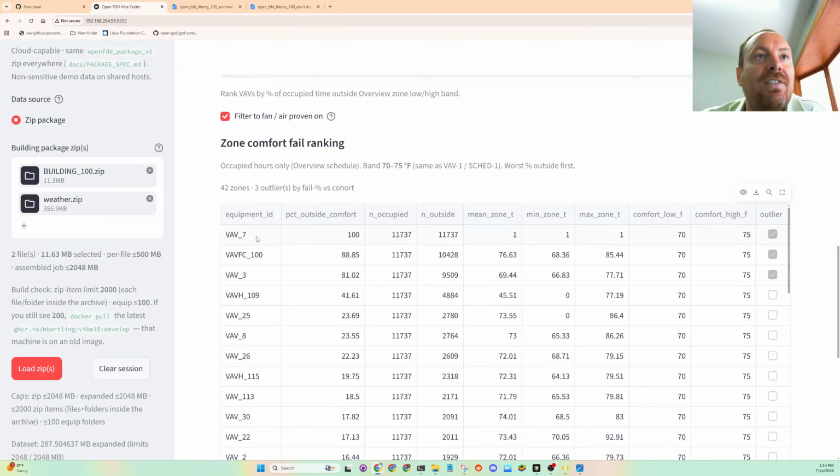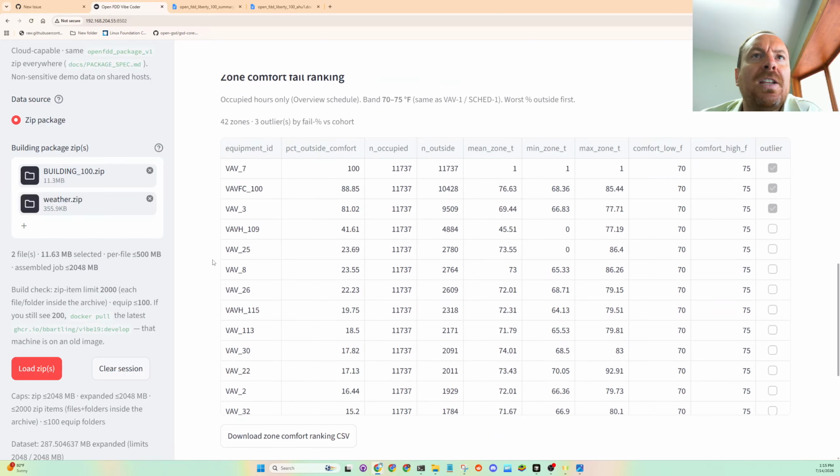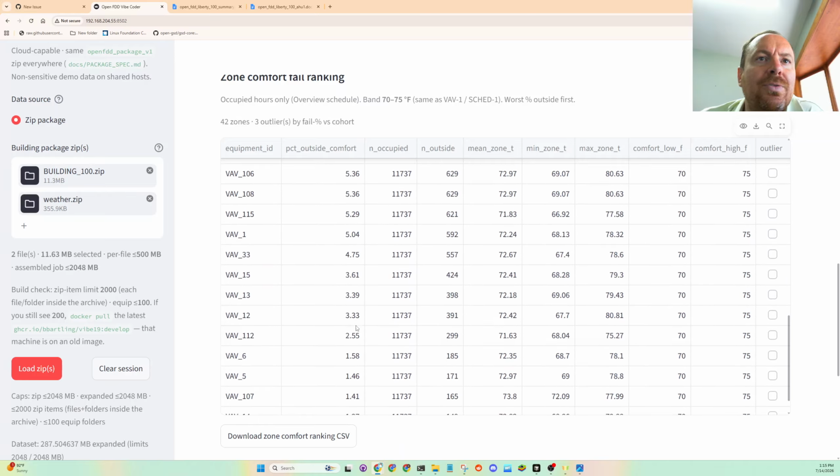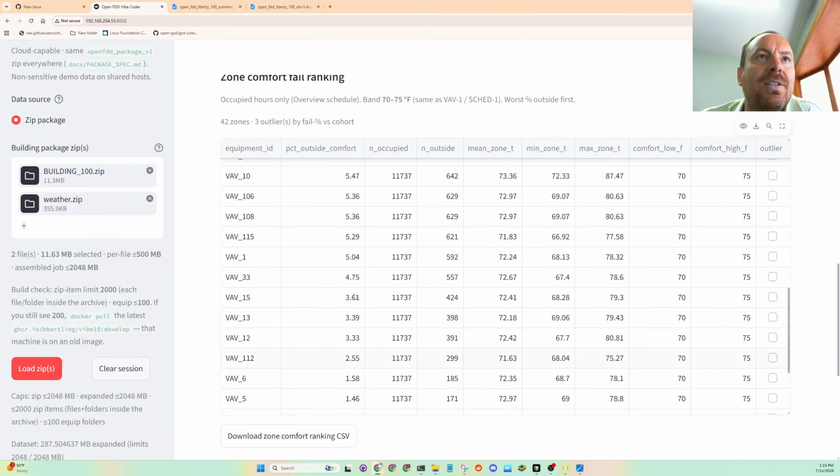So this VAV 7, 100% of the time is outside of that. VAV FC 100, 88% of the time. VAV 3, 81. And then a couple of these aren't that bad. You need to get down here, 1% of the time.